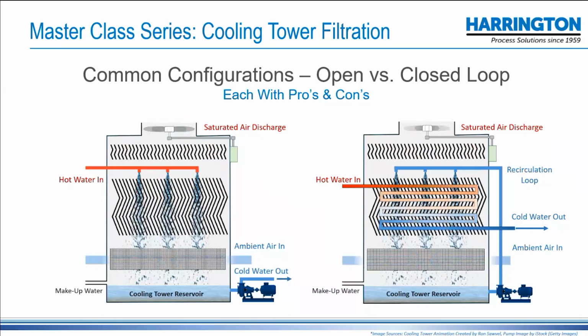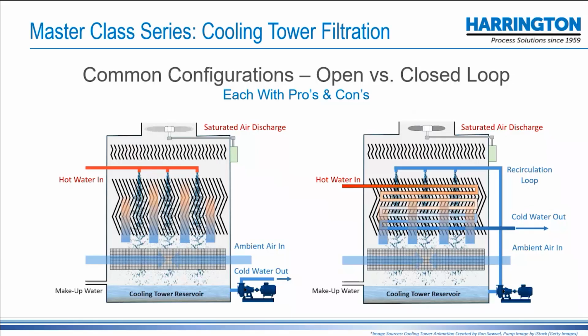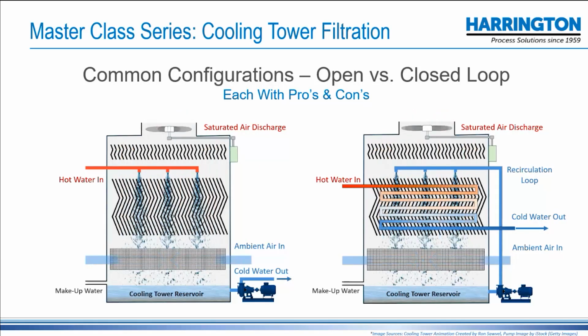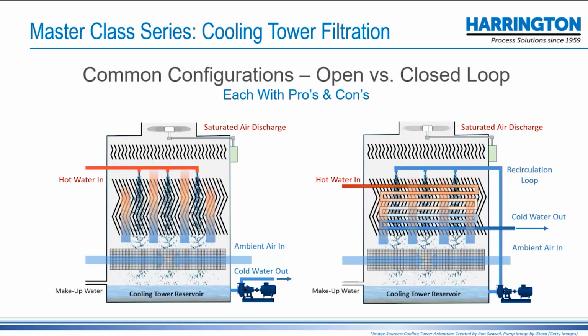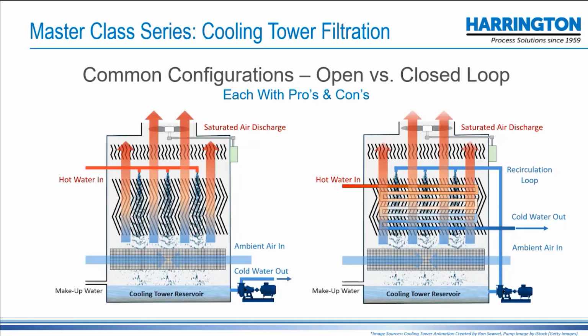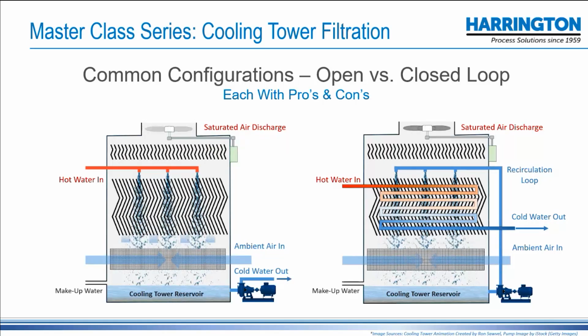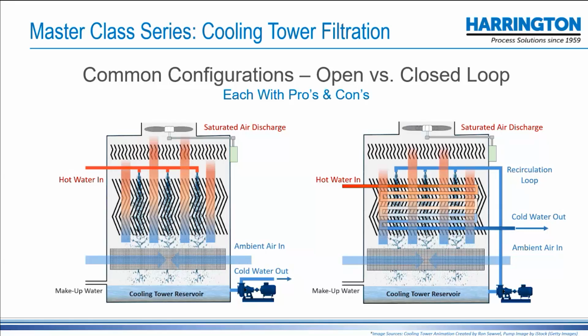The closed loop, which is now by far the more common, especially in a new cooling tower application, I don't think you'll see any open loops ever again as new systems. The closed loop is a hot water pipe that comes in, much like the radiator of a car, back and forth until it's cooled by the same process. But now the water that's cooling is provided from the reservoir in a loop, and it is sprayed down over, again, the dispersing elements, and then drops into the reservoir.